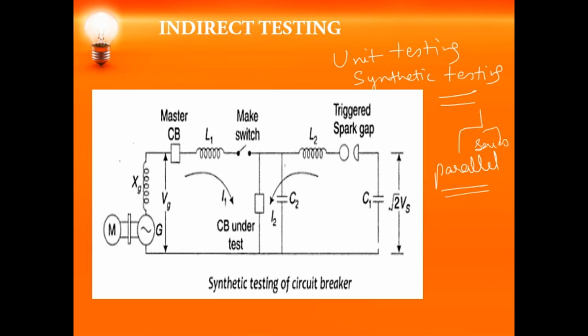If you look here, this setup is a parallel current injection type synthetic testing setup of the circuit breaker. The high current source is nothing but a motor driven generator, and it will supply a short circuit current I1 to the circuit breaker under test. This current I1 is a very high current. Next, you have the inductance L1, which controls the short circuit current. You have the master circuit breaker, the circuit breaker under test, the make switch, and the triggered spark gap.